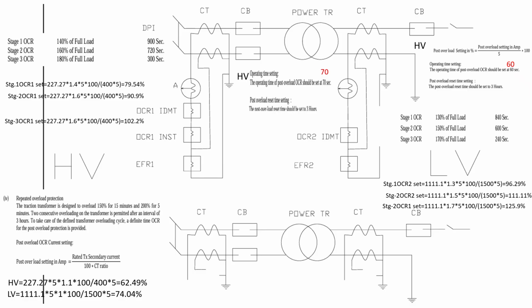And the ammeter is also there. When the current is 227.27 in the CT secondary, it will be reduced by 5 by 400. The ammeter will get that current, but it will show 227. That is calibration. The system is calibrated in such a way that during huge power circuit load current, though it is reduced through the CT, it reflects the power circuit current, but actually it is taking less current.